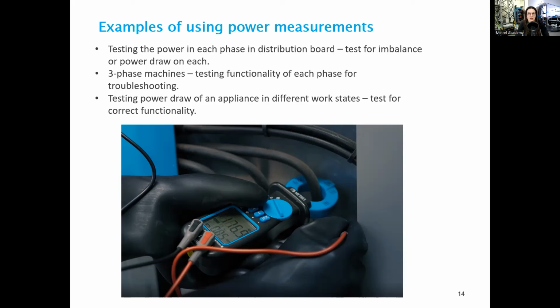Then we can use power measurements when looking at three-phase machines. So we need to test the functionality of each of the phases to troubleshoot the machine's ability to work. Then the third thing that we can look at: we test the power draw of an appliance. So now we're testing the supply to the appliance, and we are looking at different work states or operation modes of this appliance to check that all of them are working as expected, so that we test for correct functionality of a device.